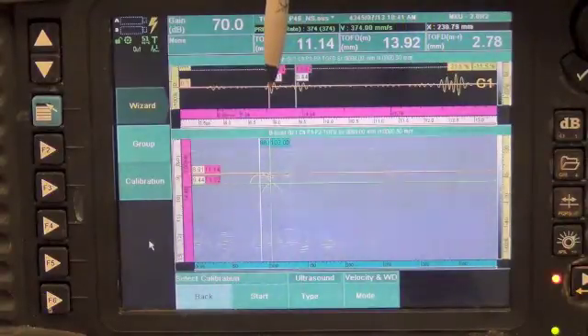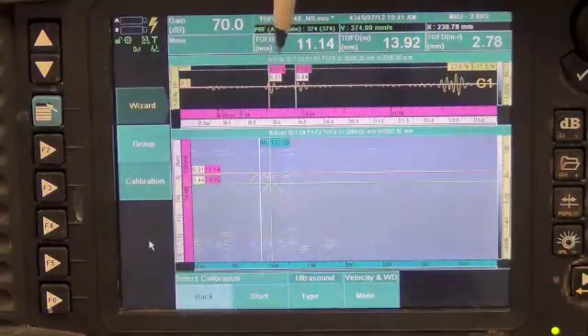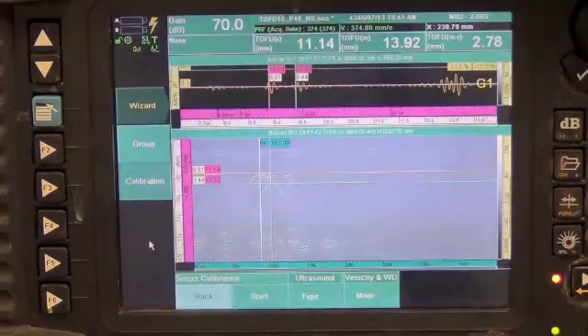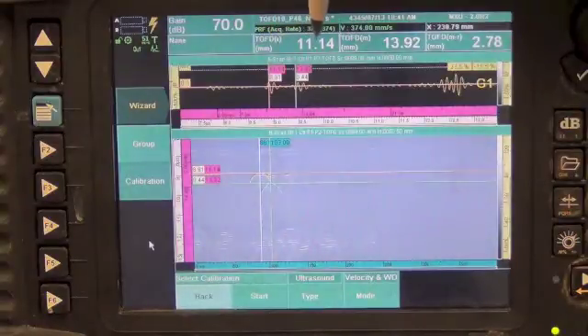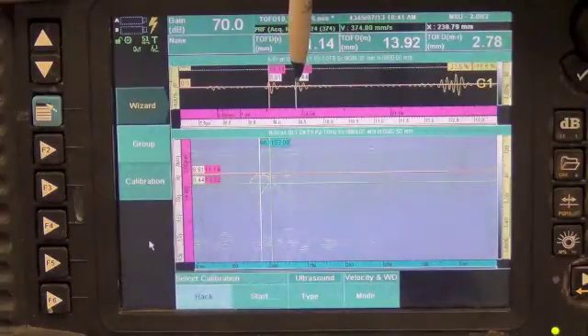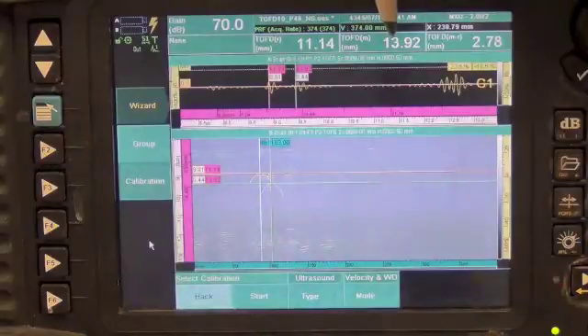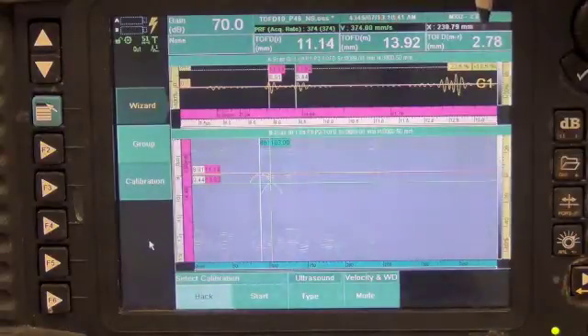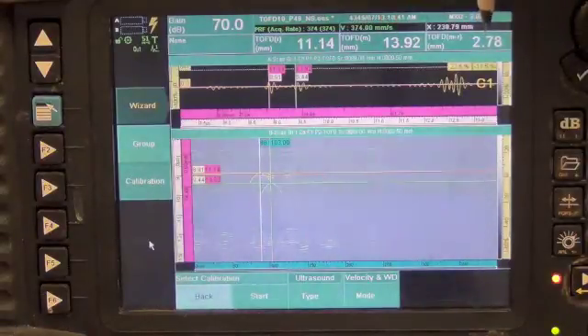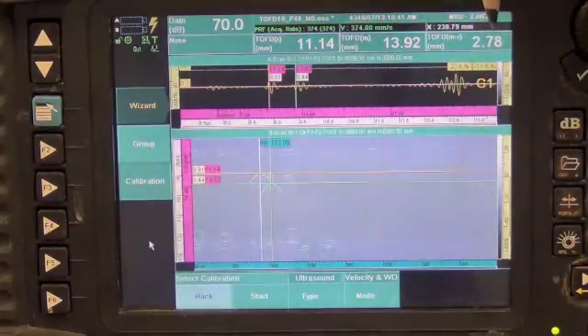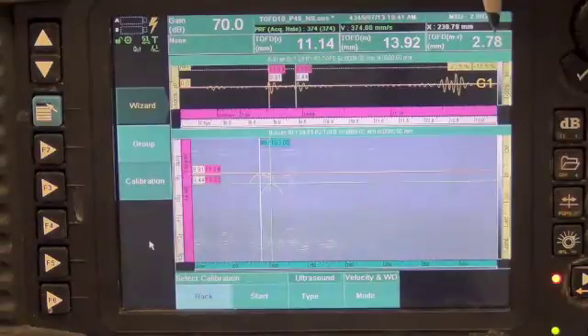This is the top of the flaw measured at 11.14mm. This is the bottom of the flaw at 13.92mm. So the flaw size is 2.78mm.